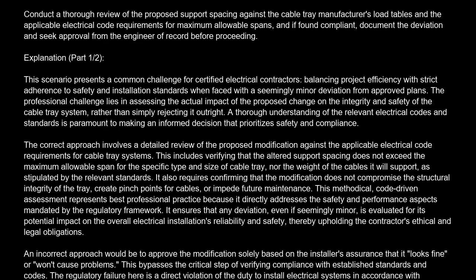A thorough understanding of the relevant electrical codes and standards is paramount to making an informed decision that prioritizes safety and compliance. The correct approach involves a detailed review of the proposed modification against the applicable electrical code requirements for cable tray systems. This includes verifying that the altered support spacing does not exceed the maximum allowable span for the specific type and size of cable tray, nor the weight of the cables it will support, as stipulated by the relevant standards. It also requires confirming that the modification does not compromise the structural integrity of the tray, create pinch points for cables, or impede future maintenance.